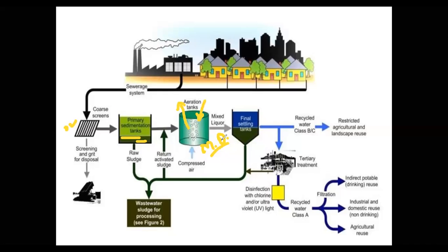Microorganisms decompose the organic impurities present in the sewage; decomposing in the sense they are degrading, they are eating. Once they are eating, they become healthy and convert into a bigger mass. Once it is converted into bigger mass, it will be easy to settle down in a secondary clarifier. Here it is shown as a final clarifier. Along with the microorganisms, some amount of chemicals we are applying also helps to coagulate the particles.